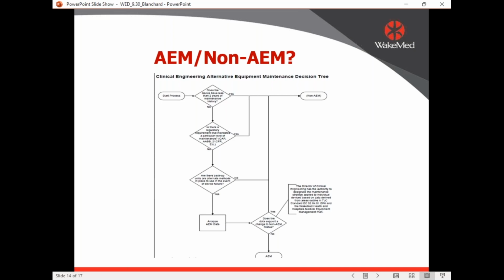And then the next step is to analyze the AEM data. We go through the history and make sure that between PMs we don't have a ton of service reports, because that's what I look for. If I have 15 service reports before the next PM, then we should maybe add another line to our PM or reduce the timeline. But if you just see PM, 1 year PM, PM, PM in your CMMS history, then maybe you can include it in your AEM. And then it kicks over to, does the data support changing the non-AEM status? If yes, the data supports it, then we drop it down into the AEM program.